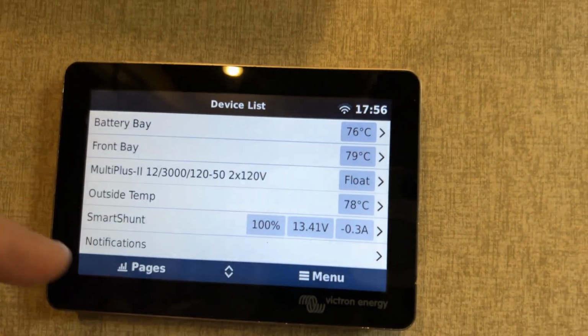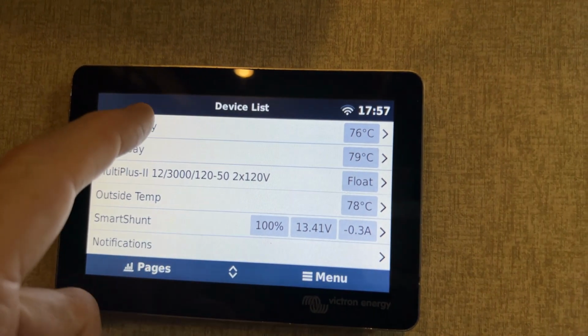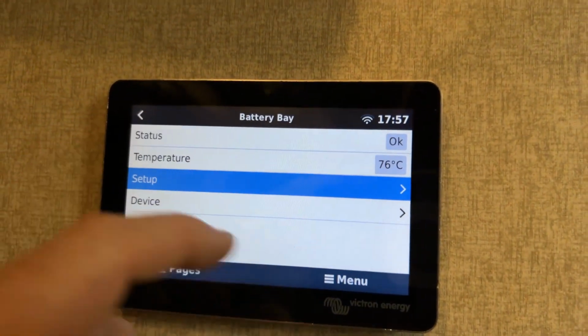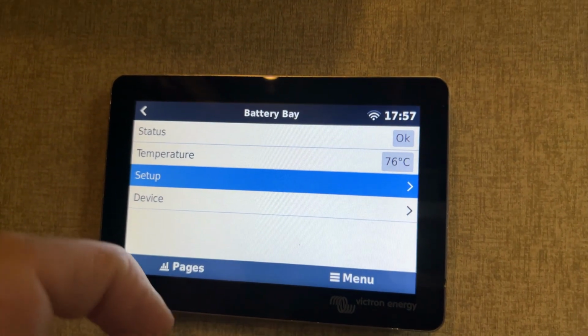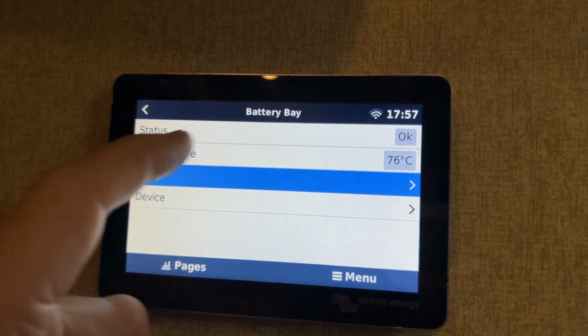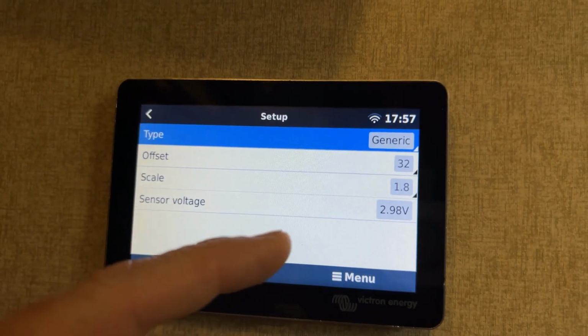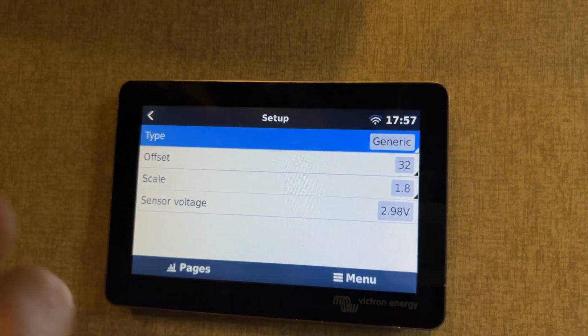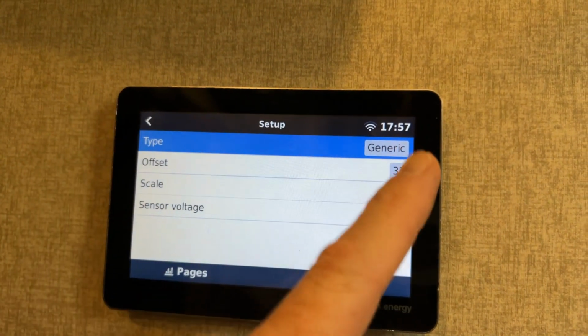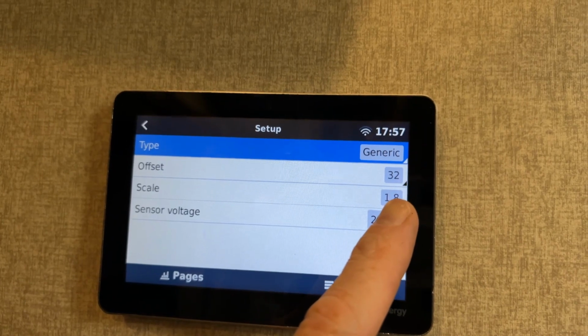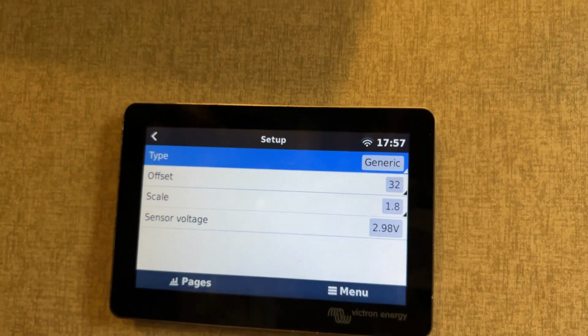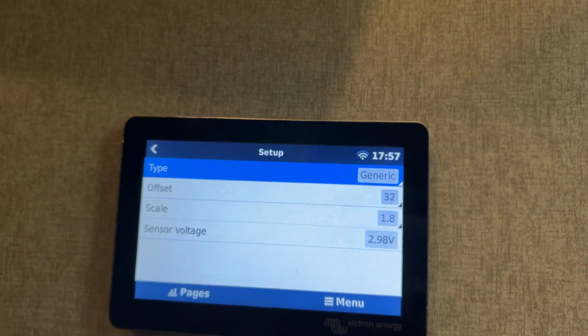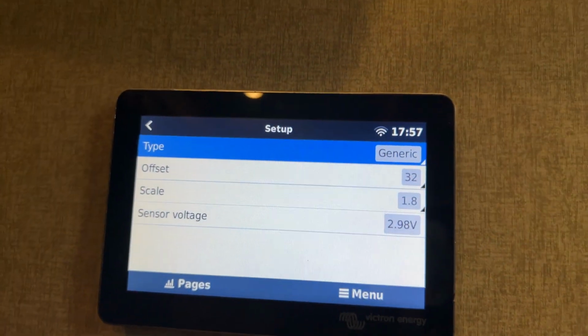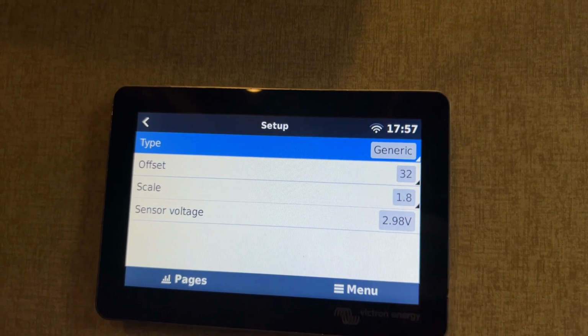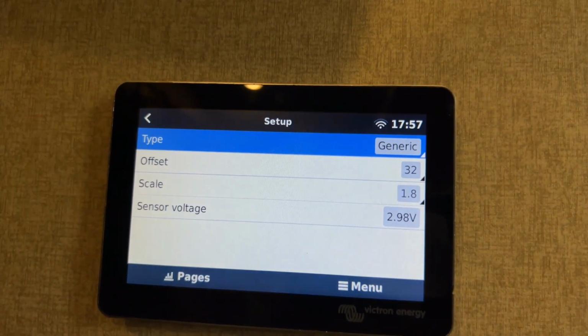To set those, once you're in SuperUser mode, you go to the actual input—these analog inputs—and go to setup. Right now it's showing temperature 76 degrees. The conversion from Celsius to Fahrenheit uses a 32 offset, starting at the freezing point, times 1.8. So it's 32 plus 1.8 times the Celsius number provided, and it also shows the voltage coming from the sensor itself.